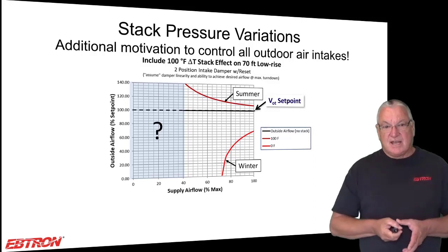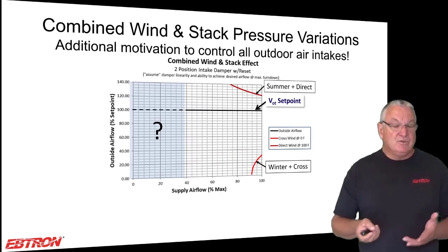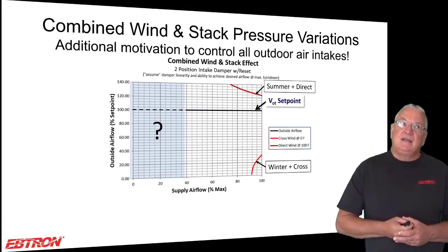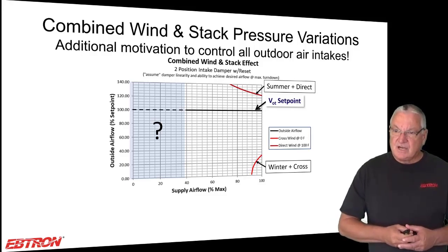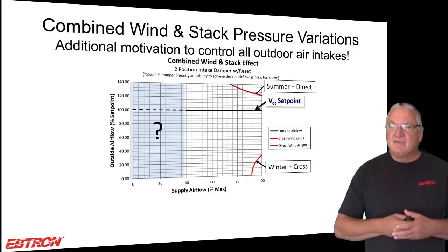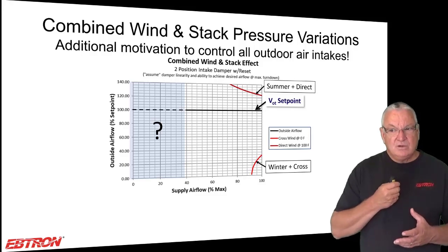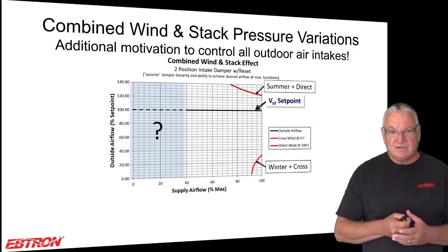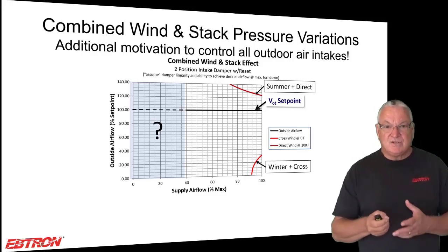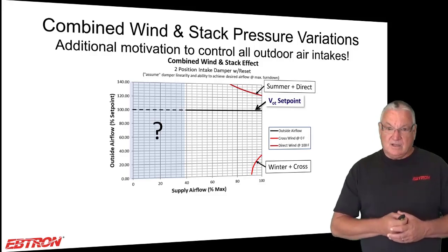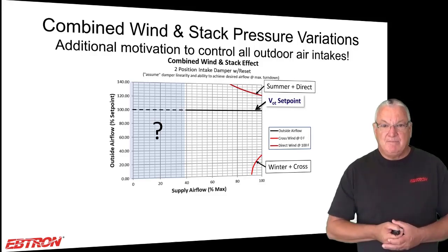And then I do the same thing with stack effect. It's a bigger problem. And when I combine the two, you really don't know where you're at. It's why you think about all these buildings that are relying on these fixed damper positions. You have these facility managers who, never mind the facility managers, even those of you that are engineers don't understand these effects, and you're like, oh my gosh, I can't control the outside air. A lot of facility people end up closing their outside air intakes because they're like, my building is out of control.